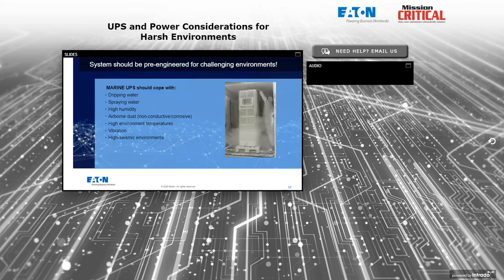The flexibility we talked about, high overload capabilities, longer overload withstandability, and that basically means a derating of the UPS hardware to handle longer term overloads, and to handle those overloads at 40 degrees centigrade or beyond. Temperature is the biggest enemy of overload capacity. We could guarantee our UPSs were all operated near freezing temperature. We could double the kilowatt rating from a given machine. But we have to be able to operate under overload for many minutes at a time if necessary without overheating, shutting down on over temperature.